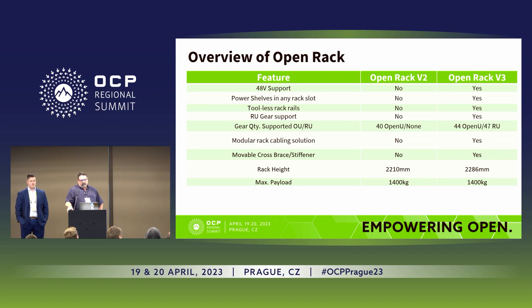This is a comparison of open rack version 2 versus version 3. V3 is 48-volt support, and V2 was not. The power shelves can be in any rack slot in V3, where they were more prescribed in V2. There's a tool-less rail kit in version 3 that you may have seen at the Rittal booth, whereas in V2 they had hardware to hold them in place. We're also supporting RU gear in V3 — in V2 it was only open U — so we're able to mix them. The rack also shows additional capacity of 44 OpenU and 47 RU.